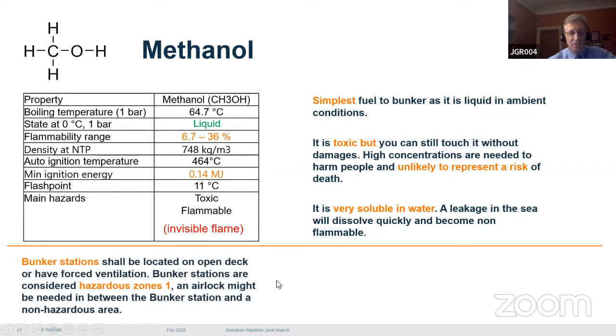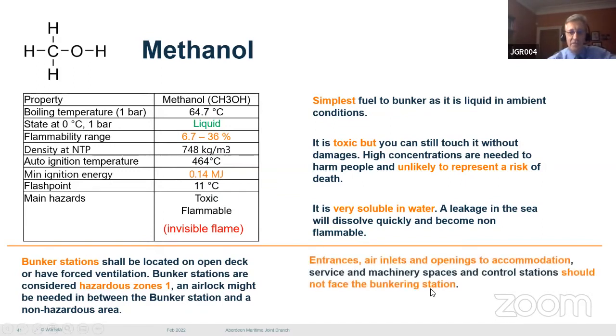Looking at bunker stations, those should be located on the open deck or have forced ventilation, and considered hazardous zone one. So an airlock might be needed between the bunker station and the non-hazardous area. Entrances and air inlets, openings to accommodation, service machinery spaces and control stations should not face that bunkering station. These are all considerations for the fuel gas supply system.